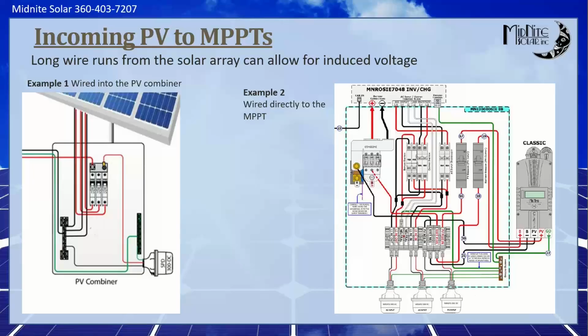That's just extra protection. But again, if that's out there at the PV array and you've got a 500 or 600-foot wire run and lightning strikes that wire, the resistance in that wire, you're going to have thousands of volts in here at your electronics. So definitely want to put it at your electronics first, and then if you can afford the second one, put it at your PV array. And this is just a couple of use cases, couple examples.